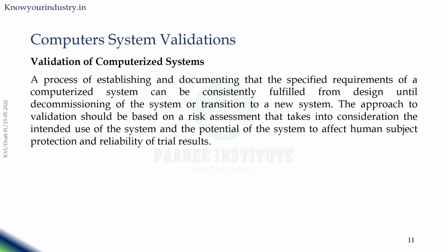So, for example, you use a software and the software needs a password. If you enter a wrong password, how many times can you try? After 3 times, it will get blocked. So this is the procedure you set into the software system. It has to be validated. So for that, a demonstration will happen and it will be recorded in a documented manner. All these things, screenshots will be captured and documented. Like this, many functions of the software, many functions of the computer system will be tested.